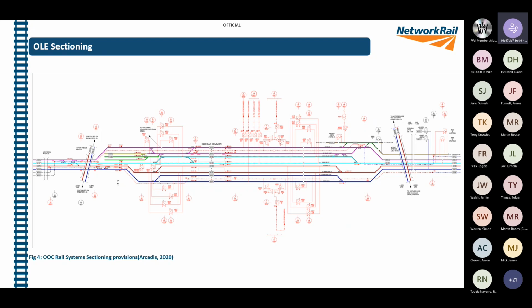This slide shows the proposed sectioning arrangement for the entire area and all the switches that will be installed. There are about 39 switches, a third of which are two-position switches, but most are three-position switches. They're all motorized and compliant with existing route requirements, enabling safer, faster isolations by remotely controlling all switches from the ECR terminals. This involves SCADA updates and LV supplies, supplied through various line side control cubicles (LCCs) installed throughout the station footprint.